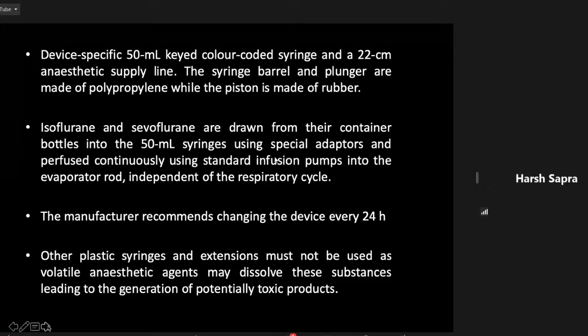So the manufacturer recommends a device change after 24 hours, but it also depends on at what rate you are running the device. We have used it for approximately, although the manufacturers don't recommend, but we have used it for 40 hours in patients of status epilepticus. Other plastic syringes and extensions must not be used, as the volatile agent may dissolve and produce potentially toxic products.